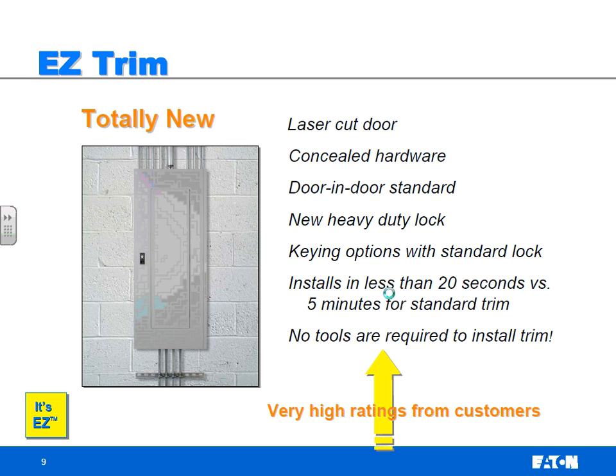I had said you've got to take it on and take it off, and if you don't have the door in door, whether the engineer didn't specify it or the cost is driving the project, it can be very difficult for a contractor to cover that every time you're trying to hook a circuit up or take a break or take a lunch. So the easy trim has the ability to be mounted in less than 20 seconds versus 5 minutes for a standard trim. Not even the door in door, just a standard trim that you have to put your bolts on.